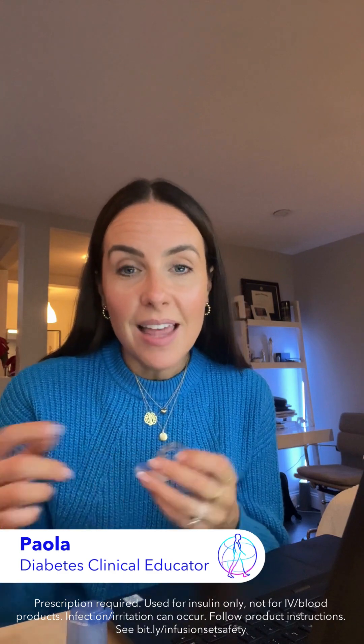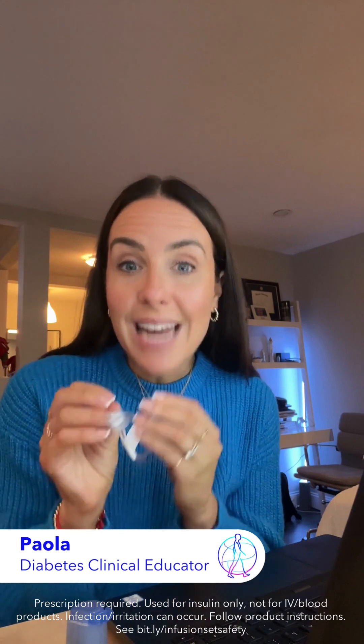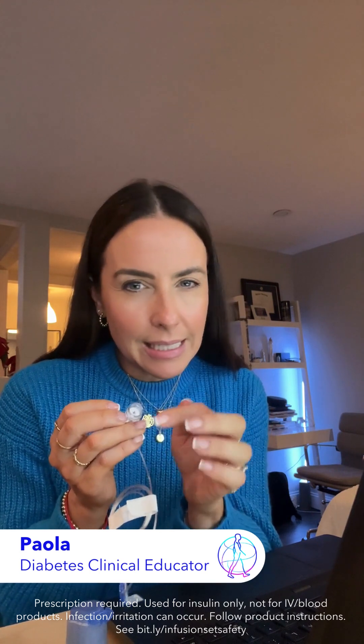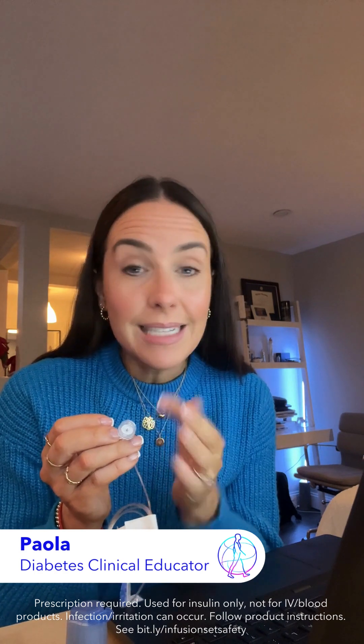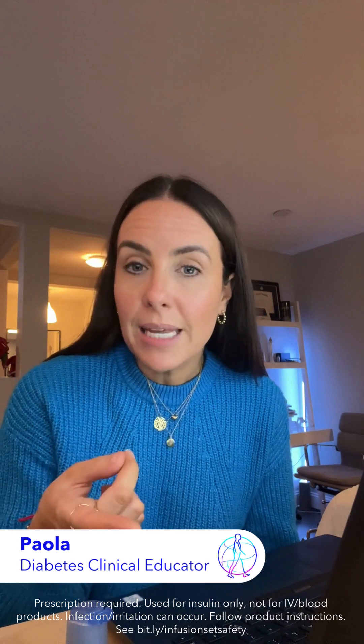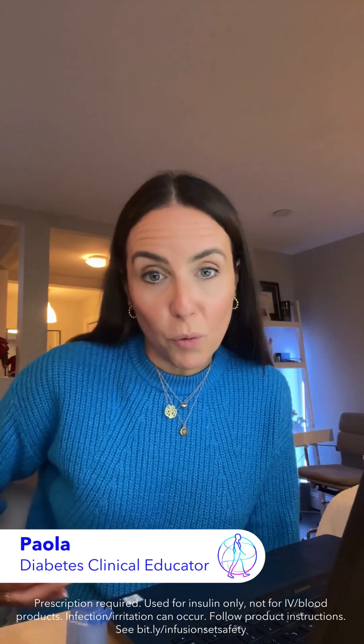This also helps extend the wear of the set and helps maintain insulin flow within the tubing. There's also a new connector — this new connector reduces the risk of occlusions, or essentially insulin particles getting stuck in that little filter and affecting the flow of insulin. This plays a part in keeping insulin stable and ensuring the infusion set at the infusion site is performing reliably.